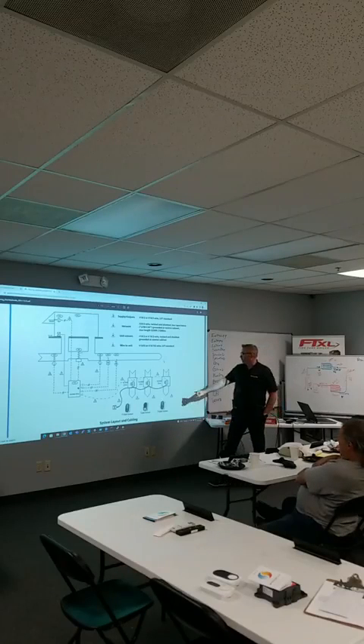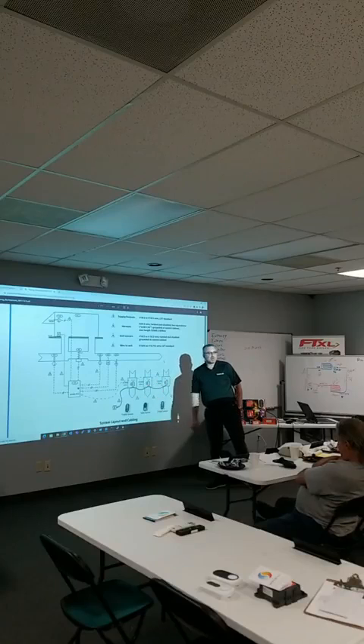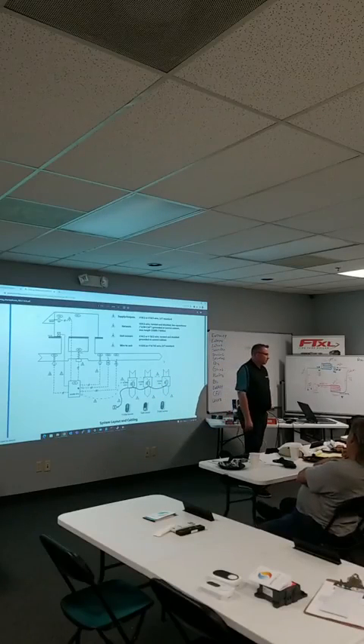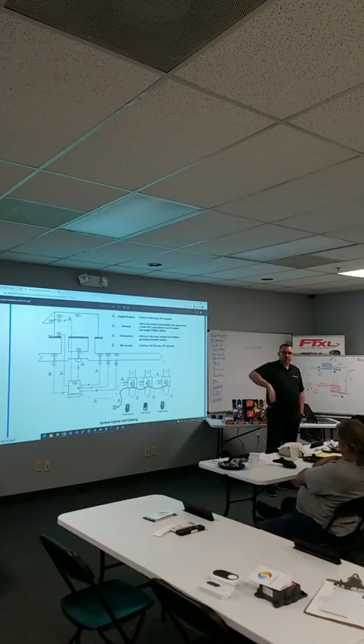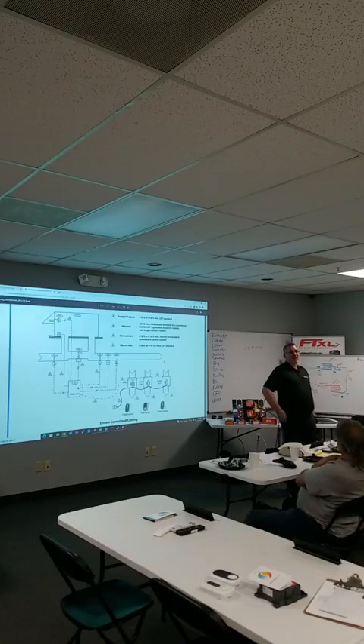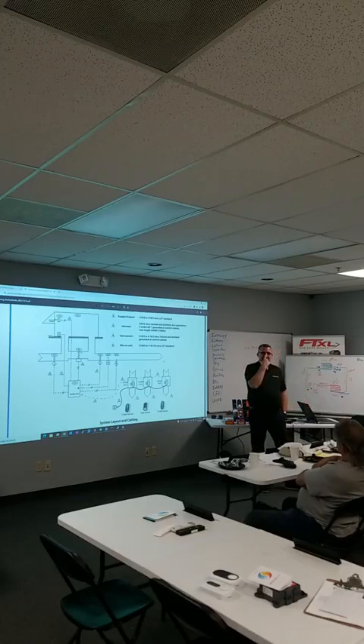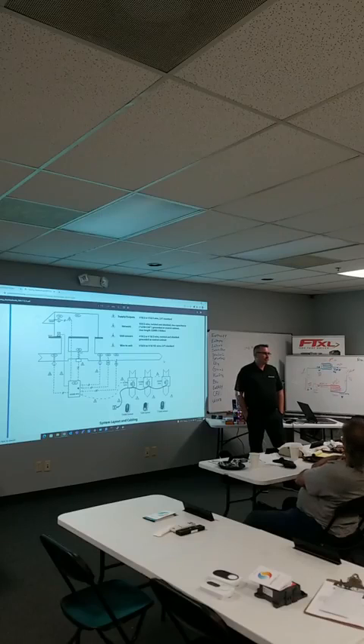The other thing we do on zone systems is actually modulate the dampers, not just open or close. So they're set to increments like 0, 25, 50, 75, 100. No, that's for testing, for commissioning, when you're looking for duct static. You can set it to whatever you want, you can do all kinds of stuff.